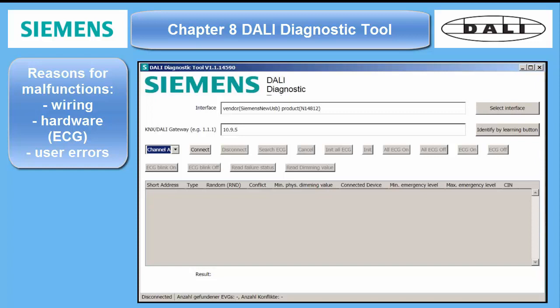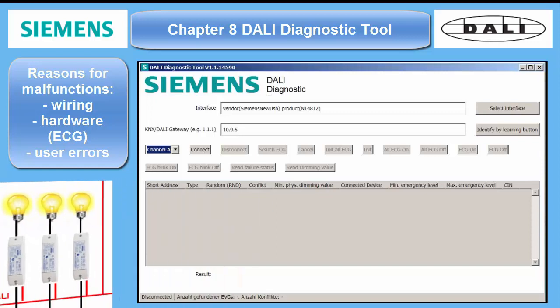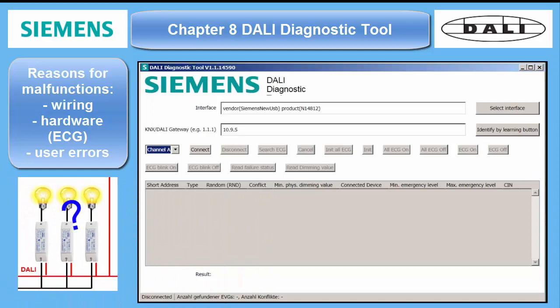For DALI, in most cases from our experience, the ECGs are causing the trouble, not the gateways.